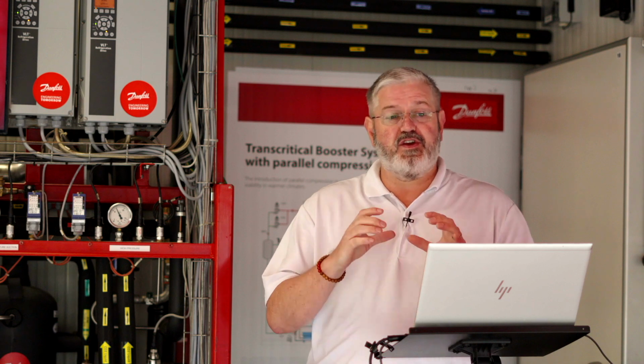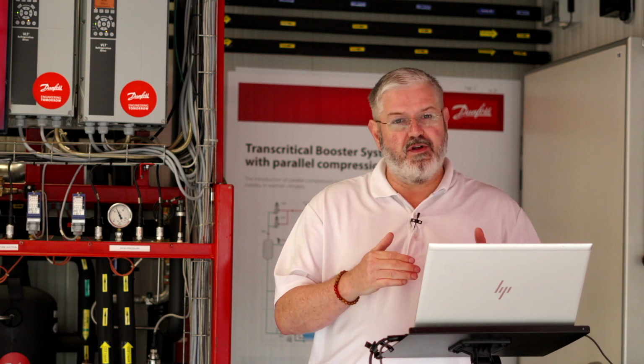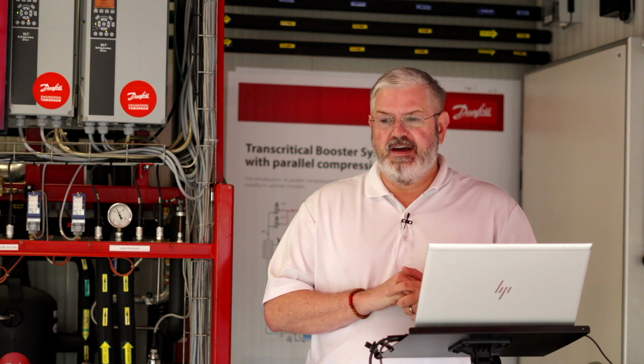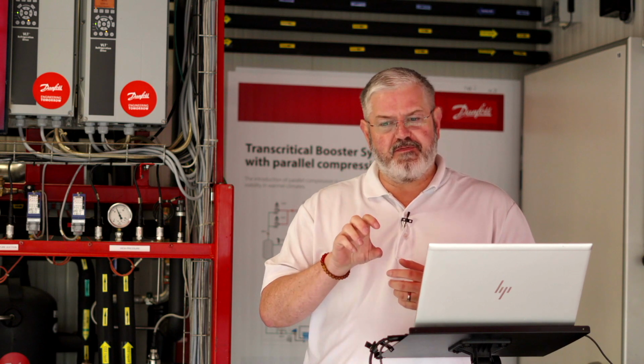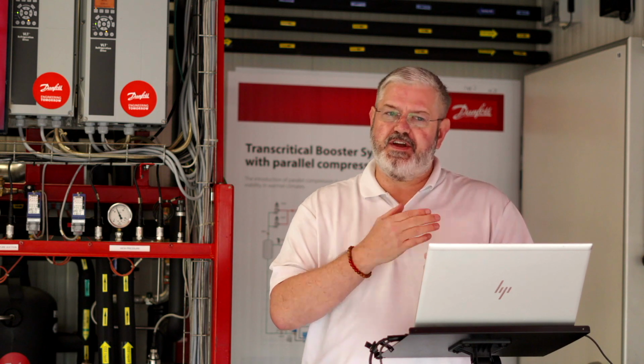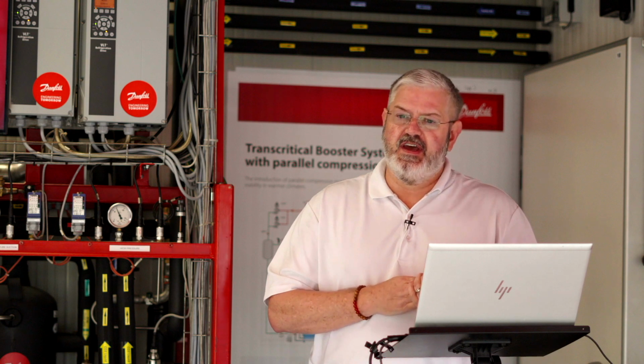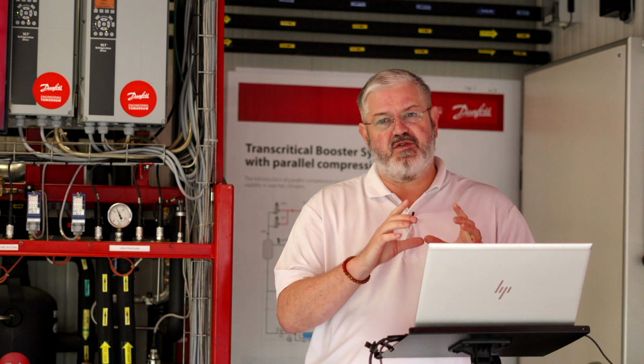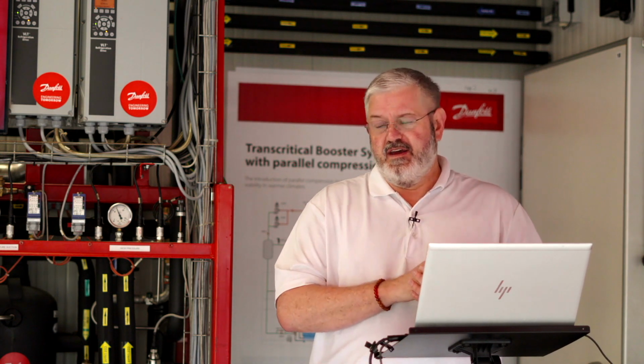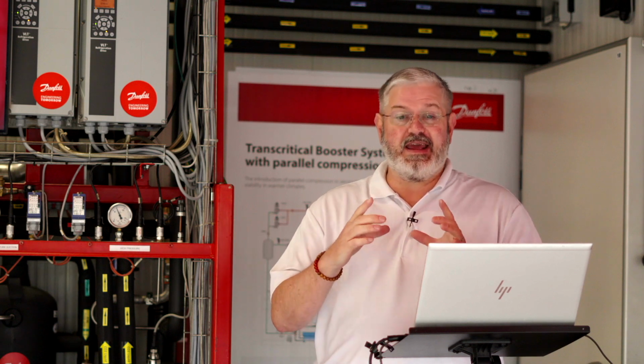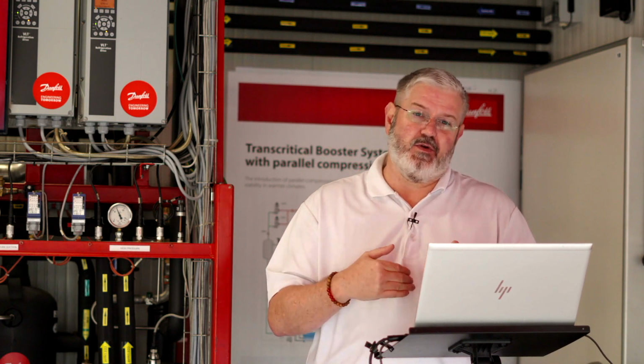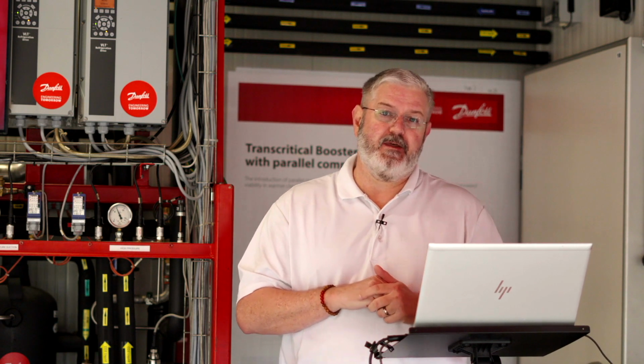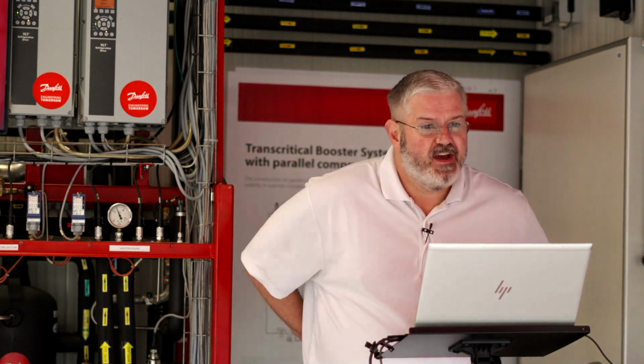We have a replacement controller for that, which is our pack controller, the 572 model. It's not a drop-in replacement, but the kit that we sell comes with the transducers you'll need, the temperature sensors. But the valve itself, to answer your question, it's not going away. And on a transcritical system, it kind of can't go away because it's what gives us liquid to send to the evaporators. I hope that answers your question.